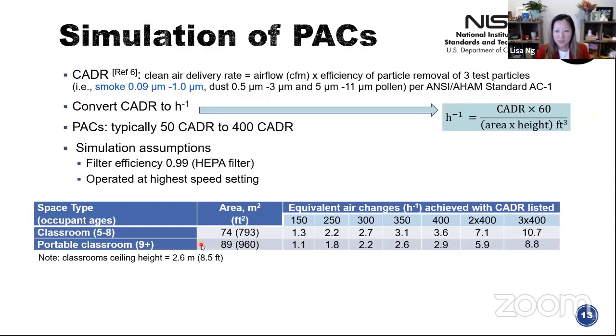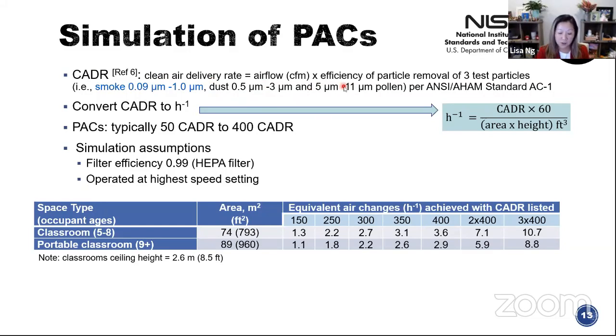I wanted to give this overview of portable air cleaners. Clean air delivery rate — CADR — is the airflow times the efficiency of particle removal. There are three test particles used: smoke, dust, and pollen. Since we're looking at one-micron size aerosols, we assume any CADR chosen is rated for the smoke particle.